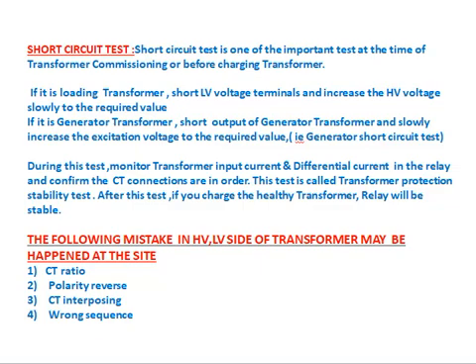Short circuit test: this is one of the most important tests during transformer commissioning or before charging. For a loading transformer, short the LV voltage terminals and slowly increase the HV voltage to the required value. For a generator transformer, short the output of the generator transformer and slowly increase the excitation voltage to the required value. During this test, monitor the transformer input current and differential current in the relay to confirm CT connections are in order. This test is called the transformer protection stability test.